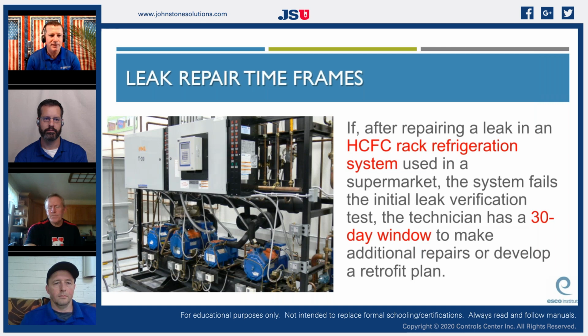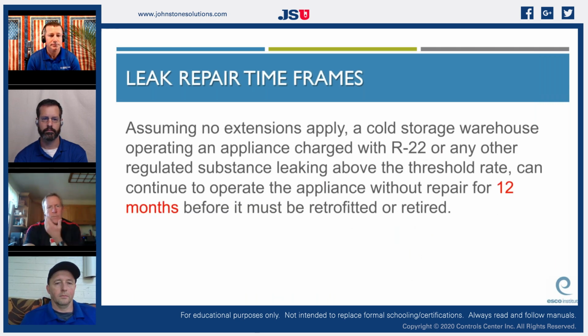Yeah, so for all of the 500 pounds and more, we did annual leak rates, and then we also did quarterly and monthly leak inspections, which we'll actually talk about as we get into some of this Type 3 stuff. But it follows into these same leak inspections. So it really depends on the refrigerant you're using, whether it is a fluorinated or chlorinated refrigerant, and it will depend on the amount of refrigerant in the system. Right. Thank you.